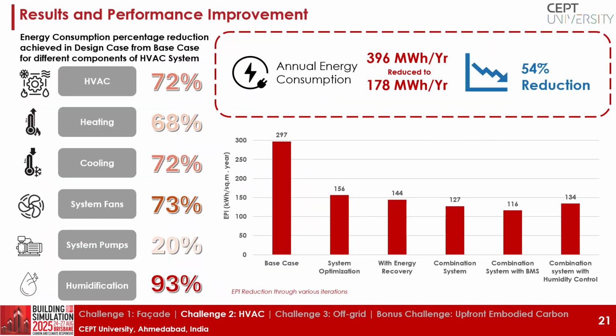Now coming to the results. The design case demonstrates substantial energy savings across all major system components when compared to the base case. Heating and cooling electricity consumption were reduced by 68 and 72% respectively, while fan energy dropped by 73%. Pumping energy, though inherently less flexible, still achieved a 20% reduction. Most notably, humidification energy decreased by 93%, reflecting the impact of optimized humidity set points and improved control strategies. Cumulatively, these measures reduce the gallery's annual HVAC energy consumption from 396 megawatt-hours in the base case to 178 megawatt-hours in the design case, representing a 54% overall reduction.